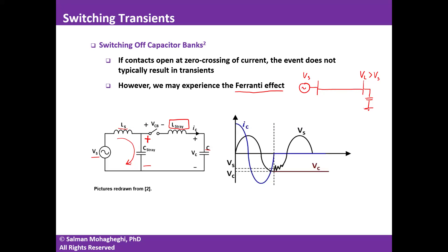At the moment the capacitor is switched off at zero current crossing, the voltage is at peak — in this case, a negative peak. The capacitor will have a voltage of negative peak, which was slightly higher in magnitude than the source peak due to the Ferranti effect. Through some oscillation with frequency determined by L_S · C_stray, the system returns to the source voltage magnitude.